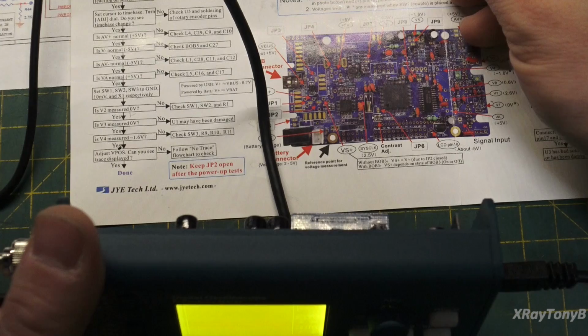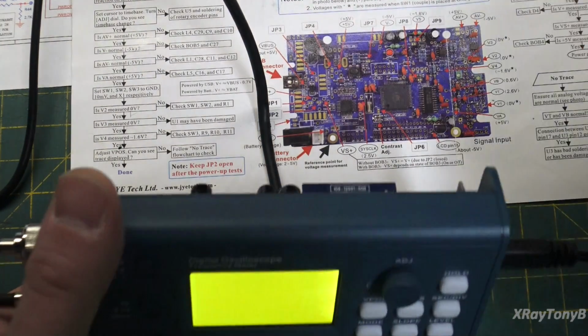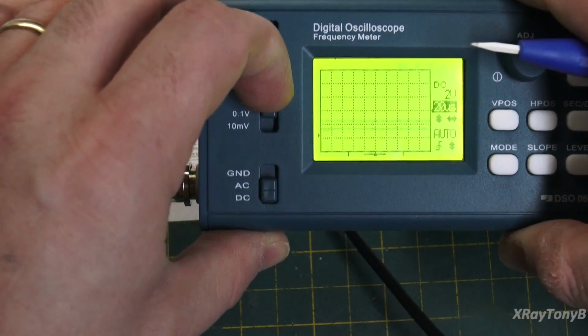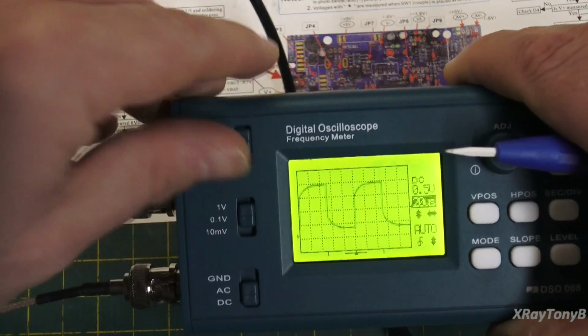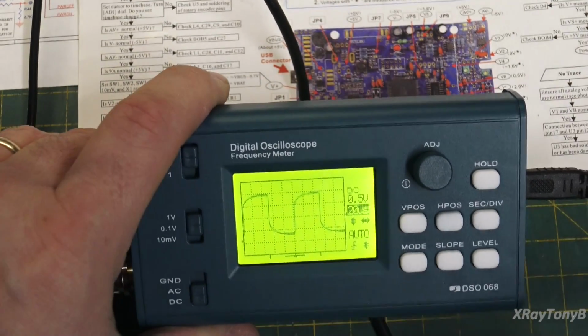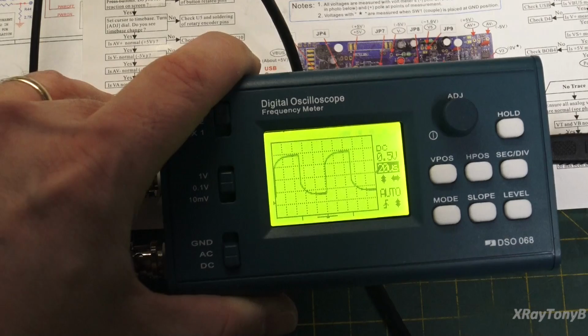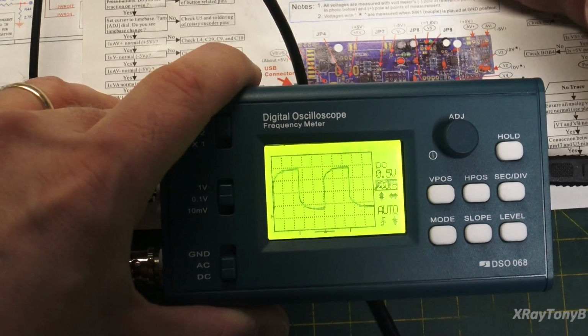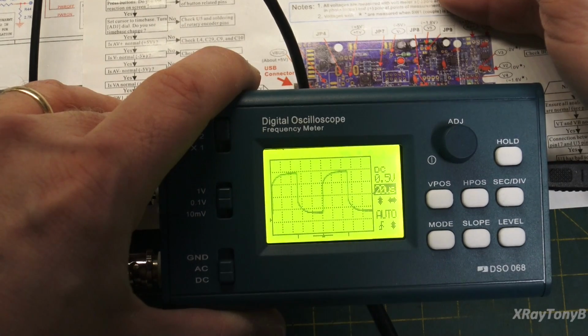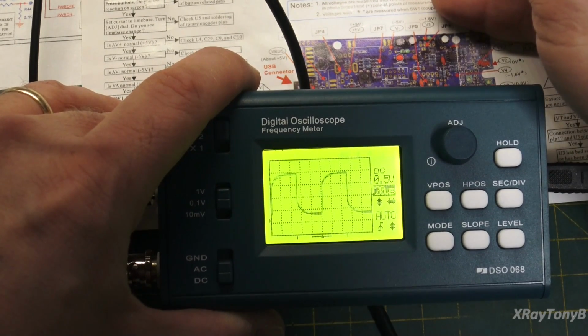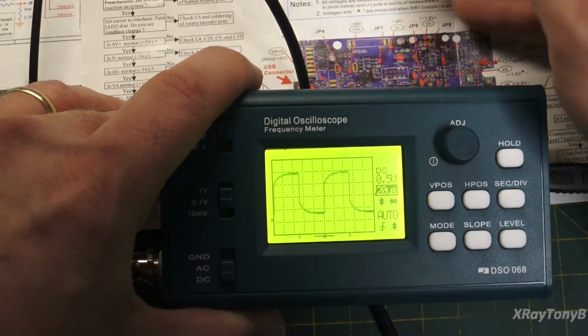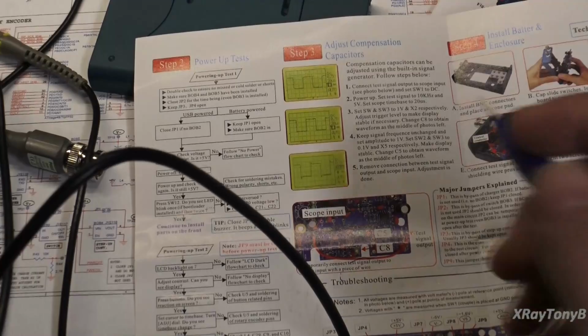Okay. Now, it says set switch 2 and switch 3 to 0.1 volt and times 5. So we're going to go to 0.1 volt and times 5. And you can see there, again, it is really grossly off. And it says make the display stable and then change C5 to obtain the waveform as in the middle of the photos on the left. Now here's the strange thing, what they're showing. I'm going to zoom you in so you can really see this. On the first adjustment, let me see here. On the first adjustment, come on, focus.